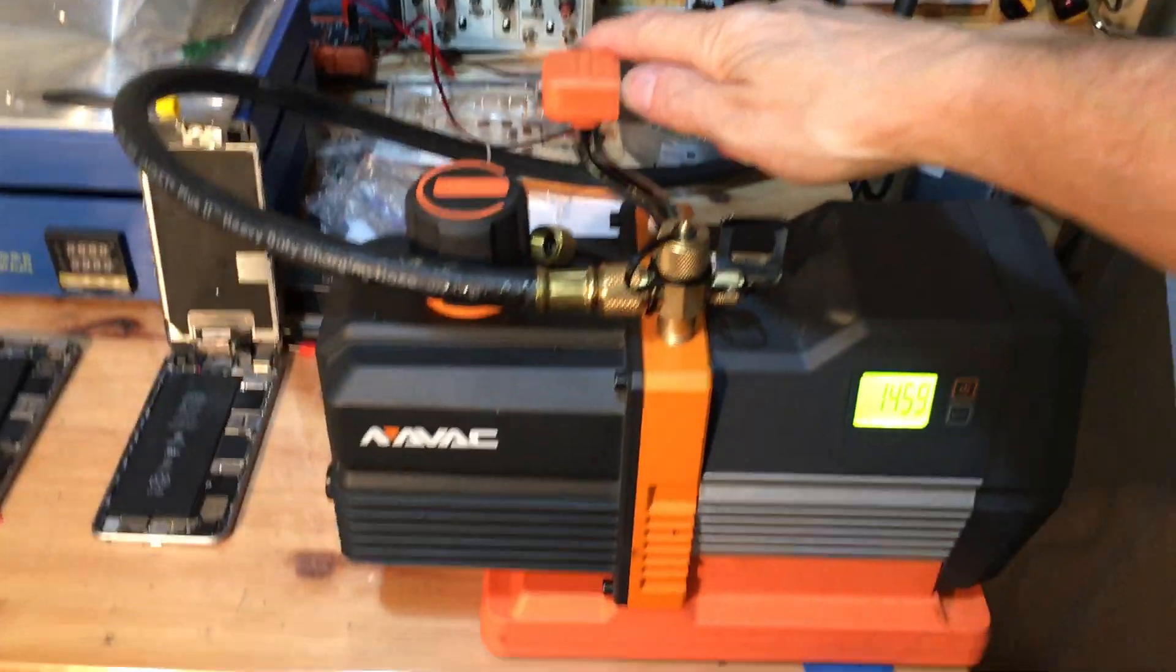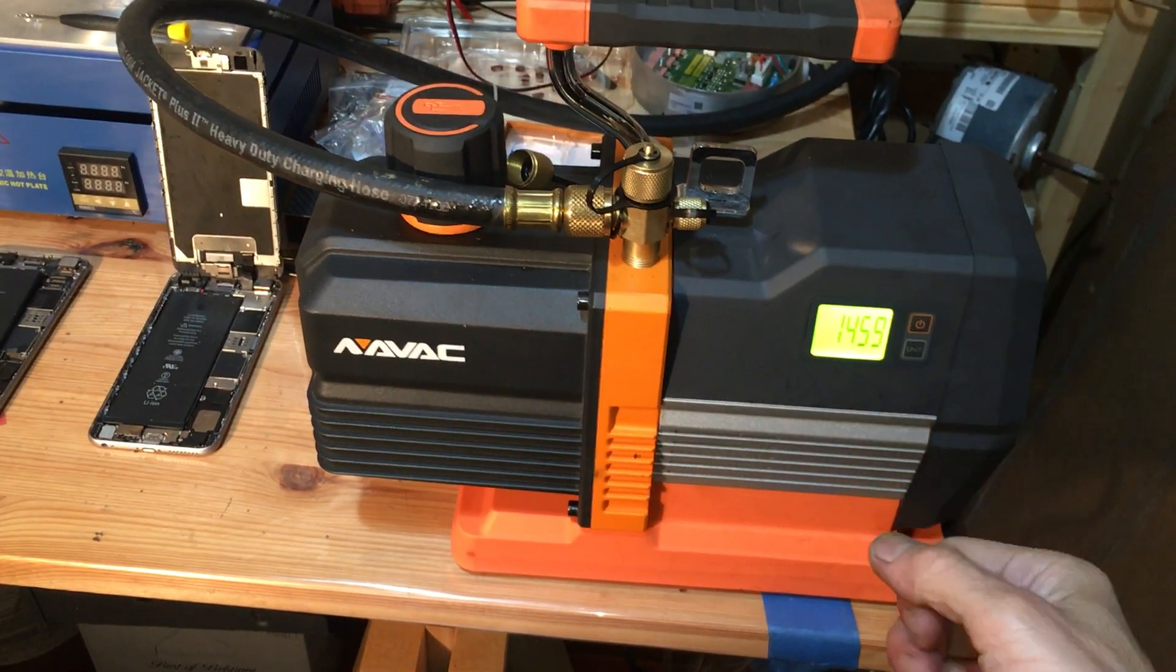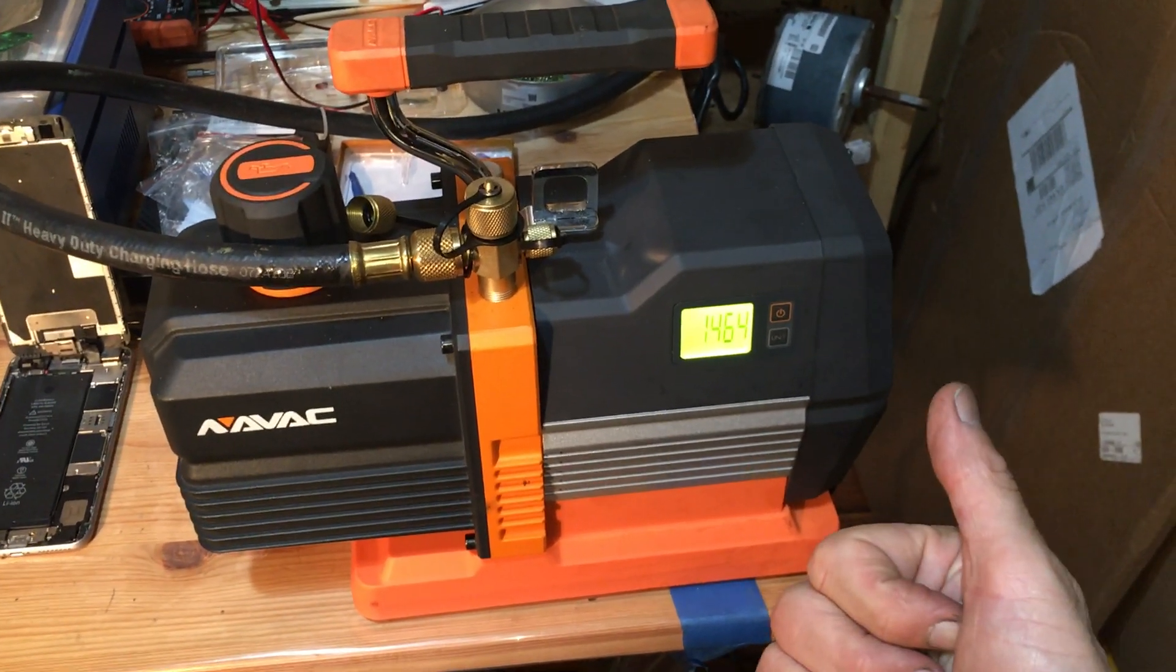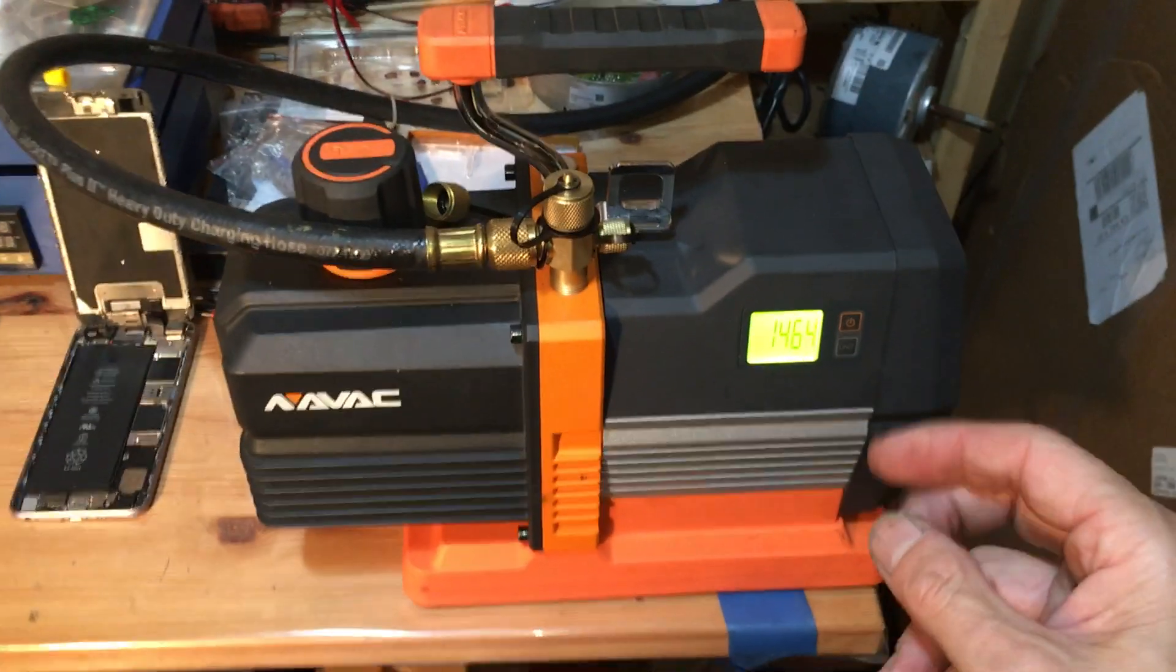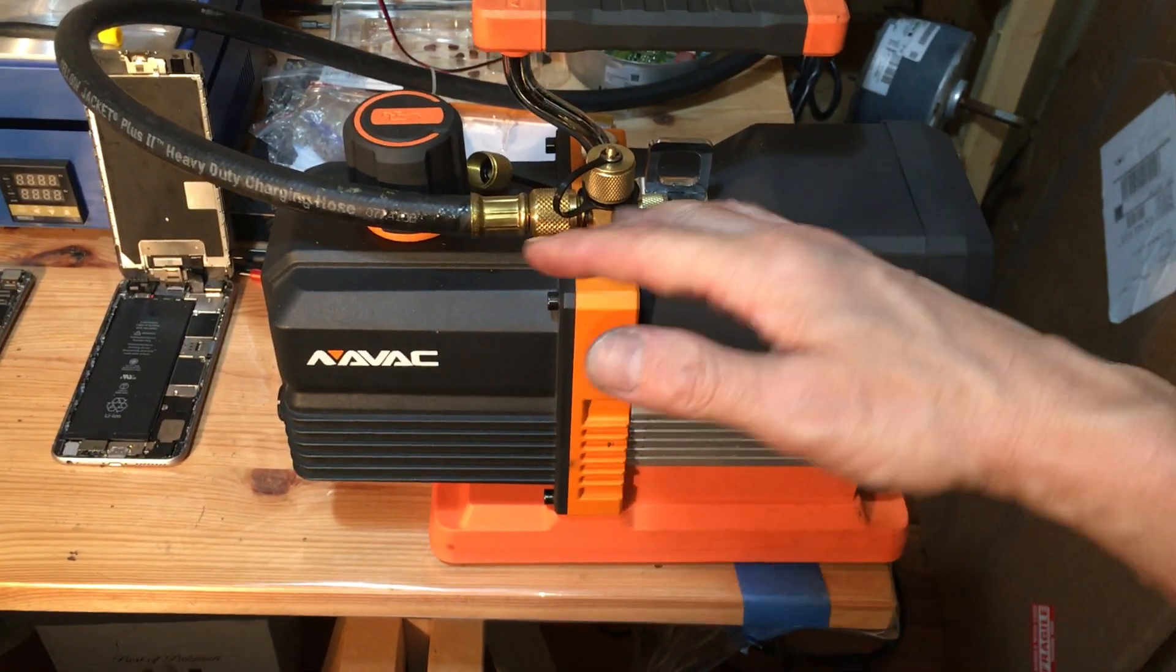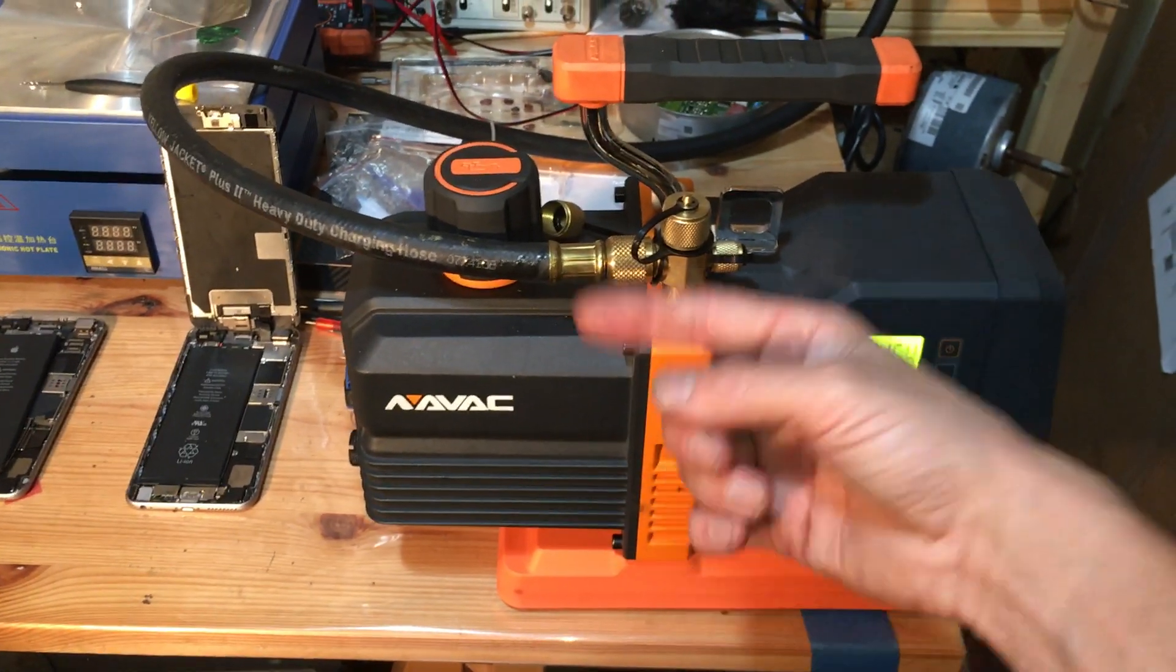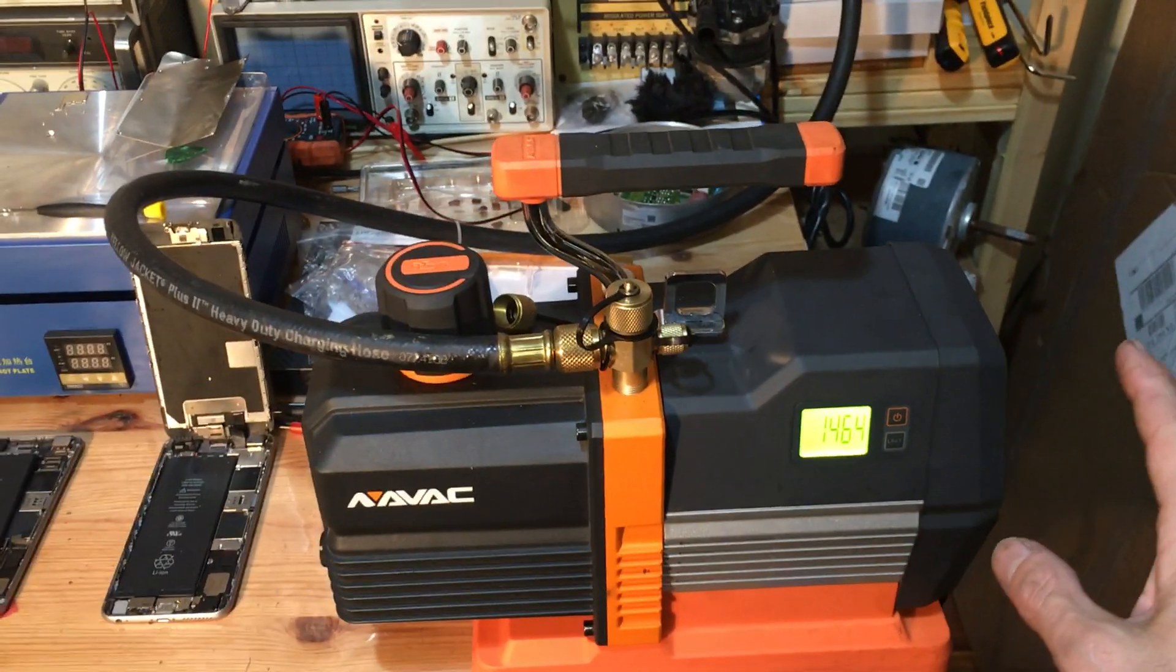A neat little feature about this NAVAC vacuum pump: when you read in the instructions, and I heard this last night because it was running in here, when it reaches 500 microns and after it reaches 500 microns, a timer is set. When it runs for 30 minutes below 500 microns, you'll hear a beeper go off and a little alarm telling you it has achieved 500 microns for 30 minutes. Then the pump goes into a lower running mode. It's no longer screaming balls to the walls. This is a DC motor, so it ramps down the motor and goes at a lower RPM.